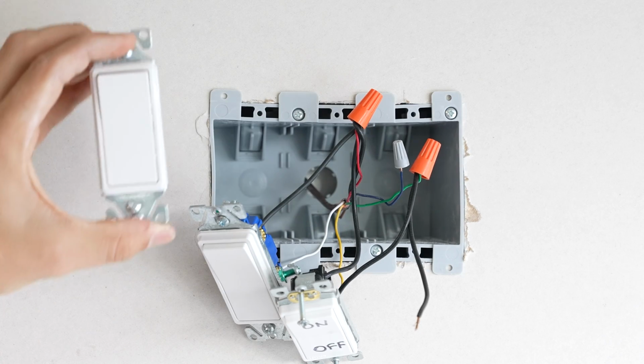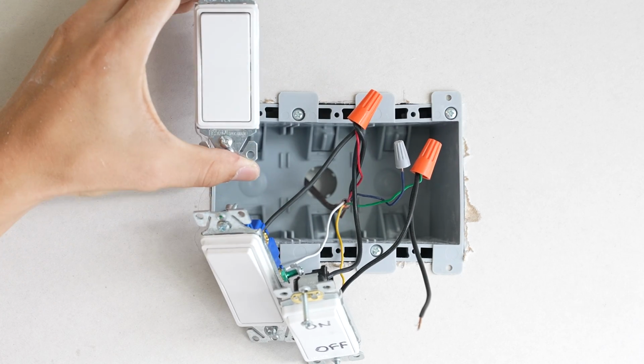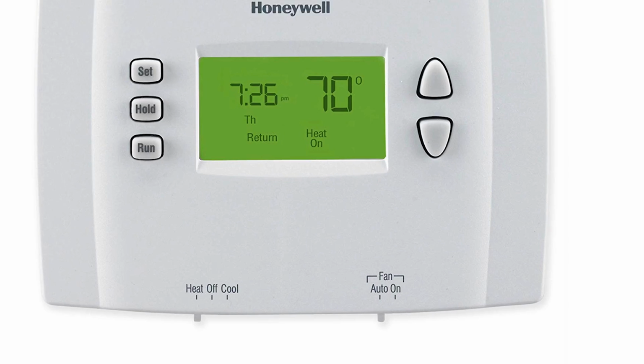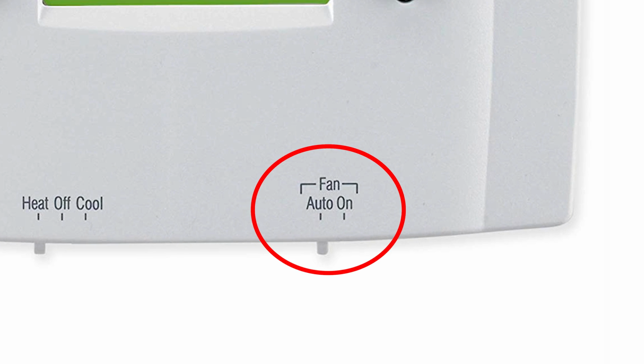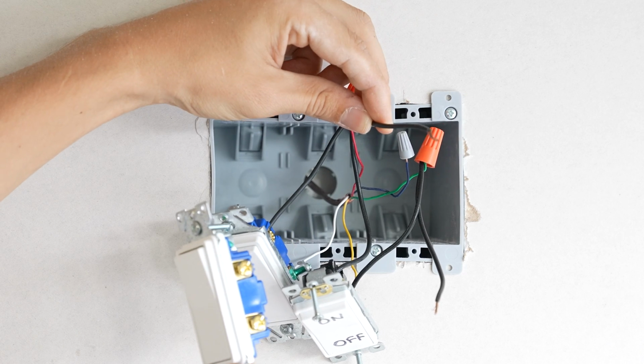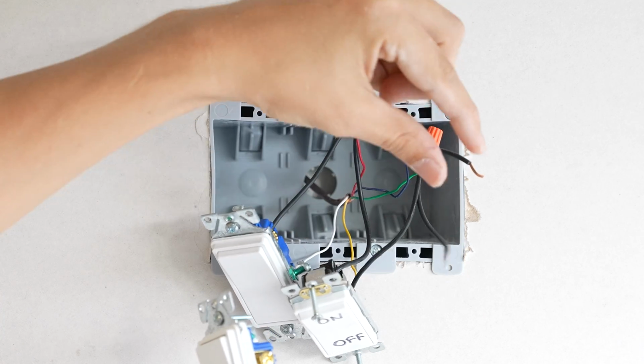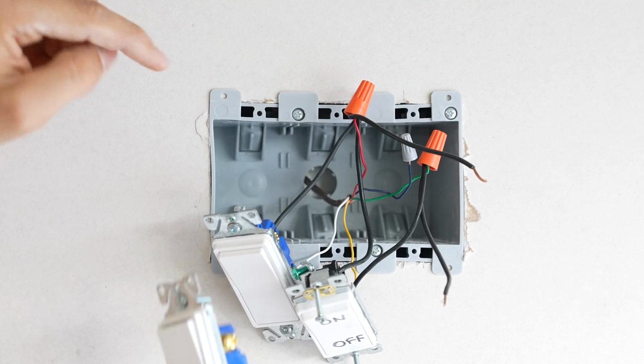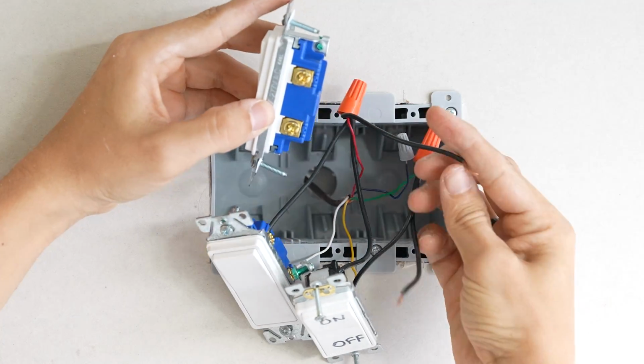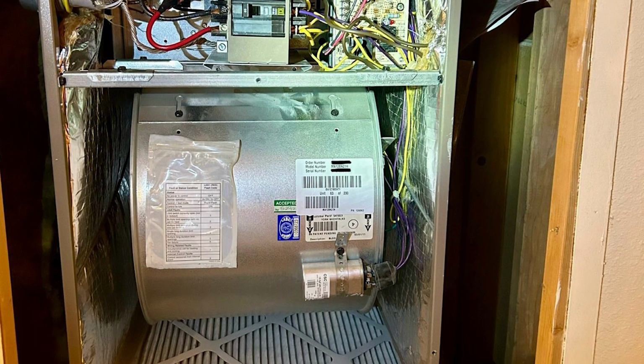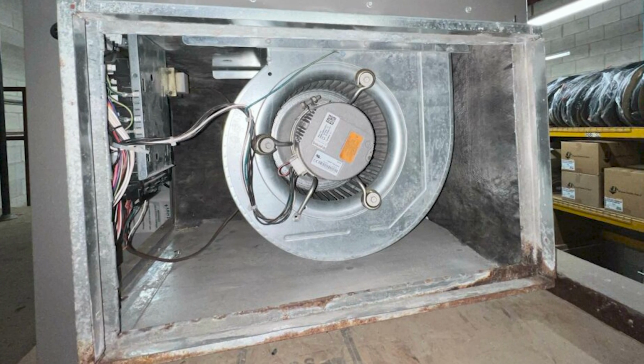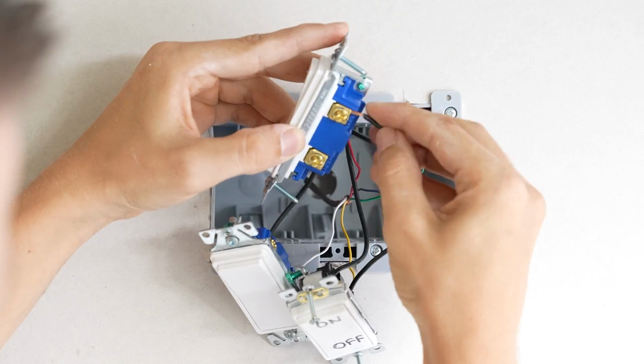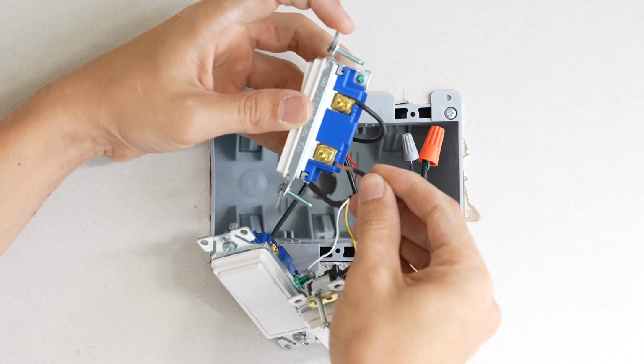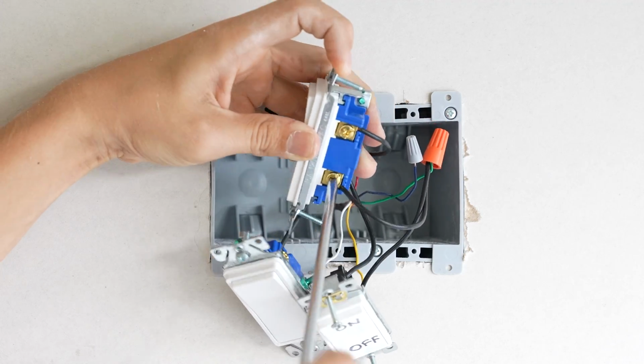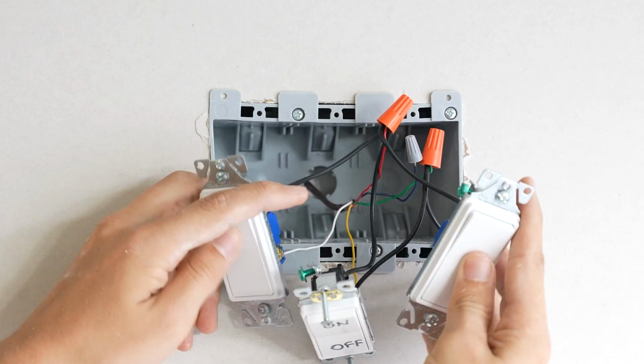The last switch will be for the indoor blower motor only. This will be essentially the same thing as a fan switch on the thermostat. Just like the previous switches, power goes in on the top and the green wire will go on the bottom. Turning this switch on will power on the indoor blower motor only, without turning the furnace or the air conditioner on. With that, all the wiring is complete.